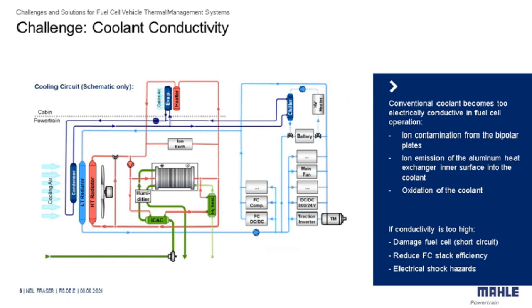If the conductivity becomes too high, this causes various issues from damage to the fuel cell, reduction in stack efficiency, through to electrical shock hazards. This, from a legal point of view, needs to be minimised, but also from a robustness point of view, needs to be minimised.